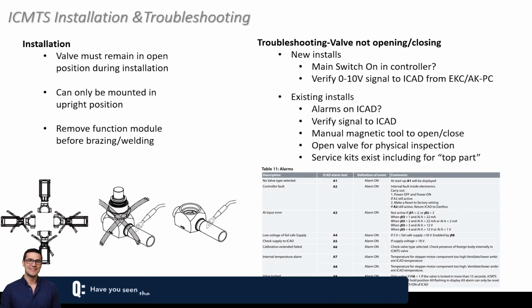Have you ever seen it where it's like 80% on the valve itself, but you're only getting 5 volts out of the controller? Like it's 80% open, 5%, or vice versa like that? Maybe it's supposed to. I can't see. I've never run across that scenario before. Usually that's something that always matches up between the controller and the voltage signal.